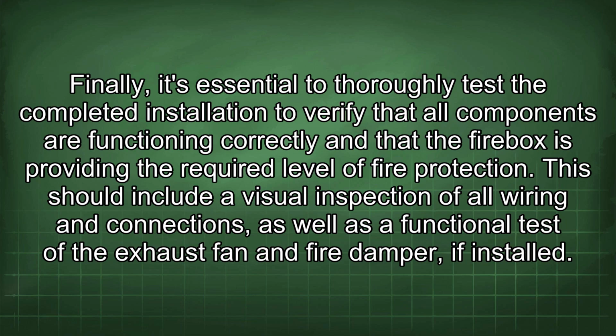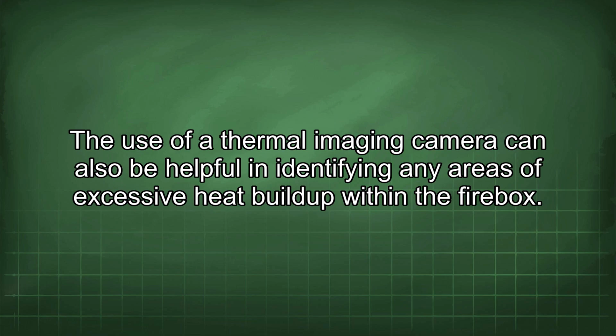Finally, it's essential to thoroughly test the completed installation to verify that all components are functioning correctly and that the firebox is providing the required level of fire protection. This should include a visual inspection of all wiring and connections, as well as a functional test of the exhaust fan and fire damper, if installed.